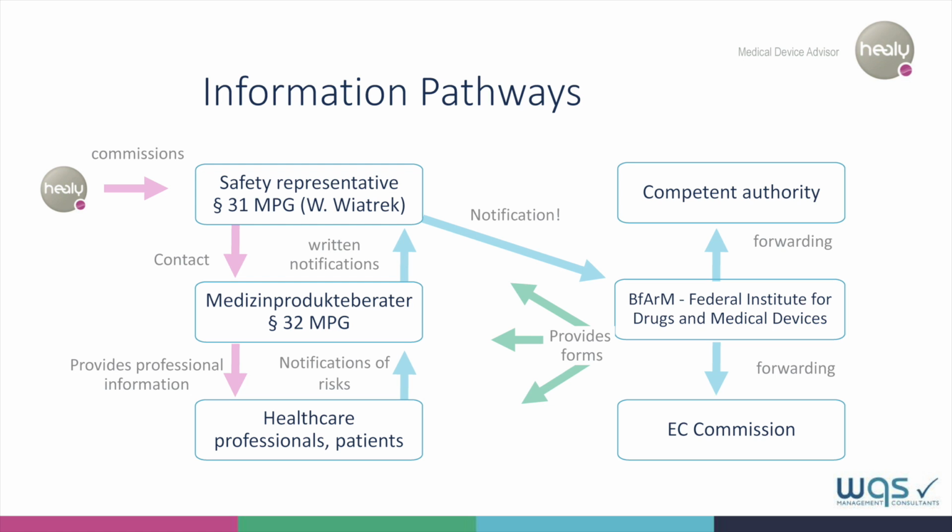The safety representative then evaluates the incoming report, and if a safety risk actually exists, reports the incident to the Federal Institute for Drugs and Medical Devices. The Federal Institute for Drugs and Medical Devices forwards the incident report to the relevant authority and the EC Commission and provides the necessary forms for further processing to all parties involved.